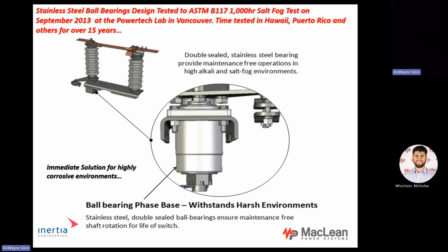So on the rotating insulator, we have a double seal stainless steel ball bearing setup. This withstands hazardous conditions and environments. We salt fog tested this, and we also tested it on the coast in Hawaii and Puerto Rico for over 15 years before we decided to put it on our switches. It allows the blade to glide very easily. This eliminates a lot of opening and closing issues, and it works admirably well. We've been doing this now probably the last 7 years. So it was a period of time before we decided to do this. And again, it separates us from other people as well.